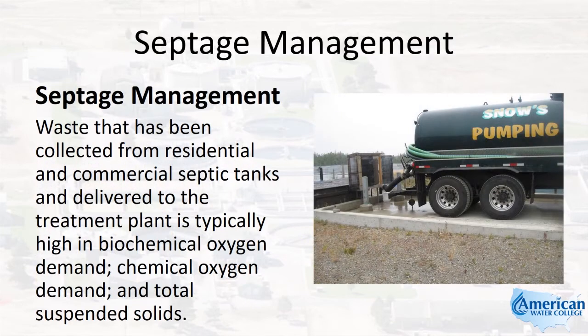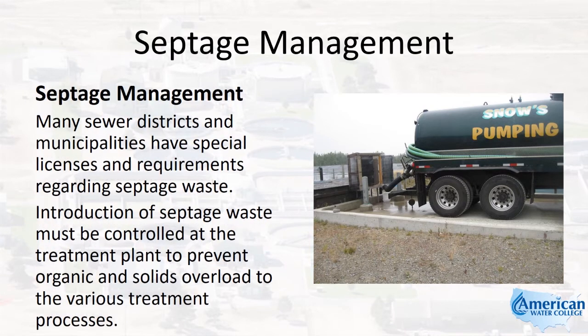Waste that has been collected from residential and commercial septic tanks and delivered to the treatment plant is typically high in biochemical oxygen demand, chemical oxygen demand, and total suspended solids. Many sewer districts and municipalities have special licenses and requirements regarding septage waste. Introduction of septage waste must be controlled at the treatment plant to prevent organic and solids overload to the various treatment processes.